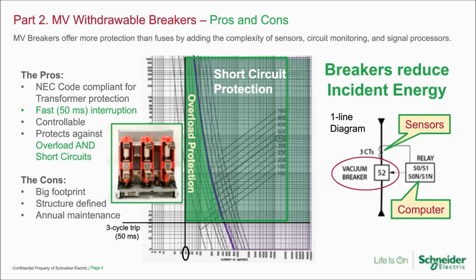The great benefit to breakers is that they address the limitation of fuses in the overload protection area. Looking at the graph, the horizontal line where it says three-cycle trip at 50 milliseconds is key. In a breaker system, the breaker movement itself happens much faster than 50 milliseconds — it only takes about half the time. But the system includes sensors, relays, relay program latency, and the breaker itself. All of that actuates in 50 milliseconds including the latency of the relay reading. Regardless of the amperage, we always trip at 50 milliseconds — totally dependent on a set point in the relay.